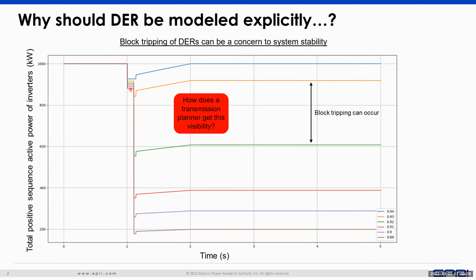We don't model everything down to the last detail, because that would take ages to run even one simulation study. So we can't model every load and every piece of equipment in full detail. Instead, at certain voltage levels we carry out aggregation. Traditionally in North America, load is aggregated at the 69 kV voltage level, which is basically the distinction between the distribution system and the subtransmission or transmission network - anything below that voltage is aggregated.